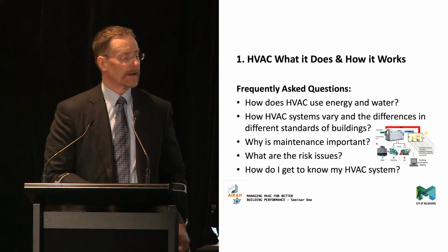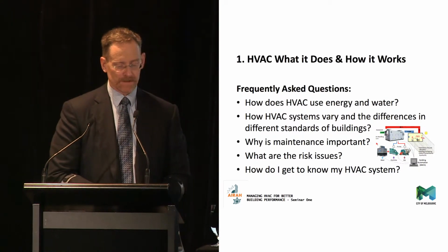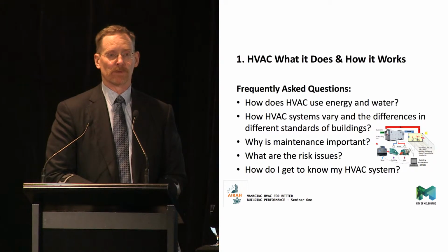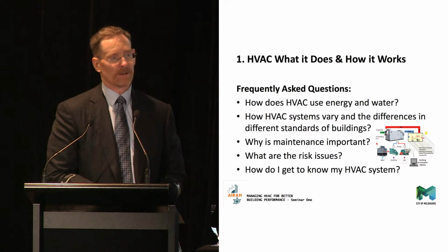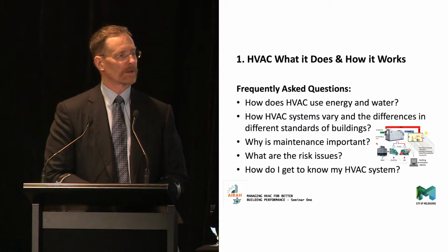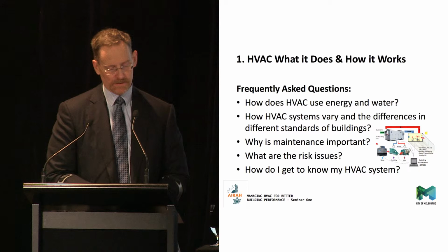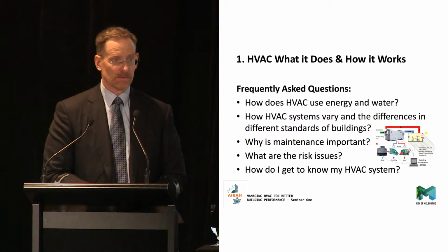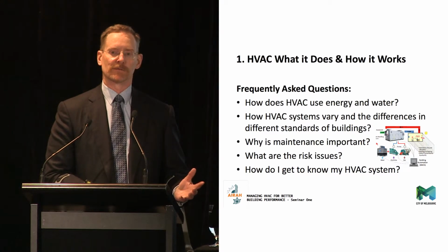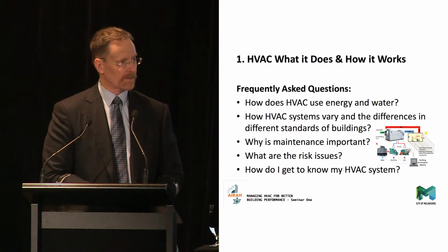So how do HVAC systems vary? Obviously they don't all look like this. This is very much a generalisation. There are 101 different variations on the whole process. One of the important variations, I suppose, that we've seen in the last 5 or 10 years is chilled surfaces, chilled beams. A number of you might be familiar with the term chilled beams. Council House 2, which was mentioned before, has chilled beams. These are effectively cooling or heating surfaces in a space that actually radiate heat or cooling, but they are cooled by chilled water, they are heated by heating hot water, so the componentry is the same. You have chillers, you have boilers, you have those sorts of things as well. You still have air handling units, you still have an air distribution system, you still have all those things I mentioned before. Another option is a refrigerated system, so you take the concept of a refrigerant and write it large, if you like, and so you effectively have almost like a split system you have at home with no water. These probably aren't that common these days.